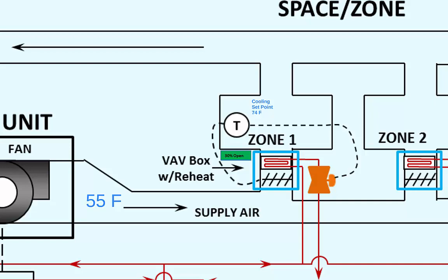Maybe the room temperature will settle at 72 degrees Fahrenheit, in which case the controller will just keep minimum flow going through the VAV box. But if the space temperature continues to drop, it will eventually reach a predefined heating set point, which we will say is 71 degrees Fahrenheit in this case. If the temperature drops below this heating set point of 71 degrees Fahrenheit, that would indicate to the VAV box that we are now in a heating scenario.